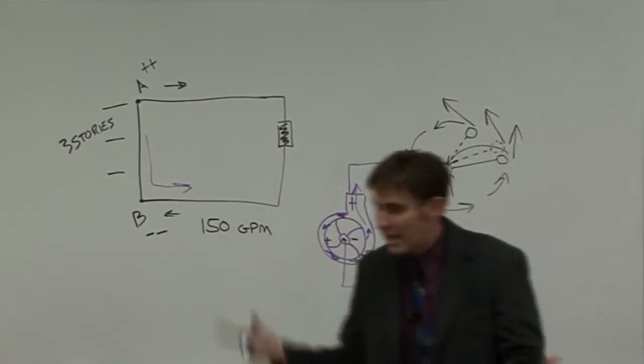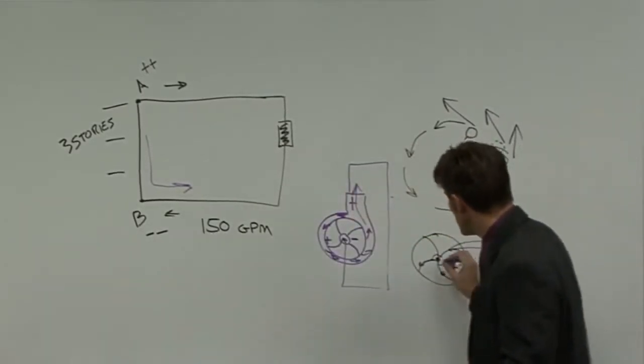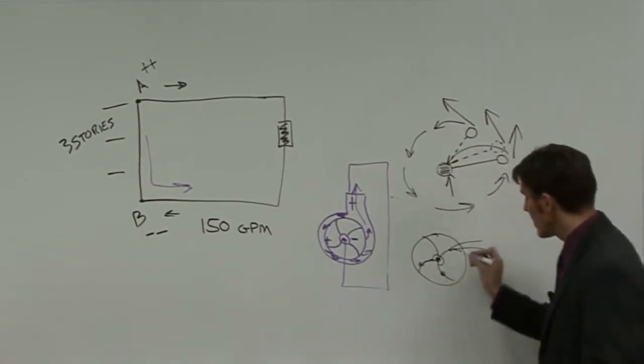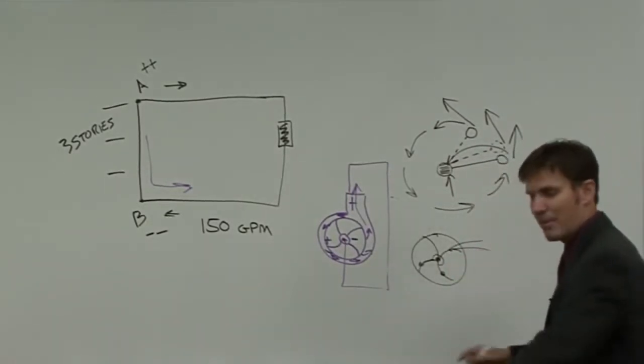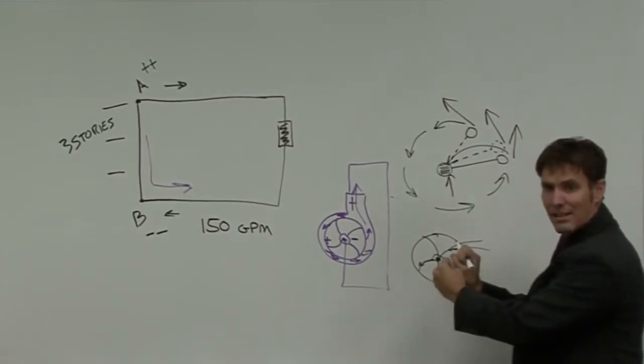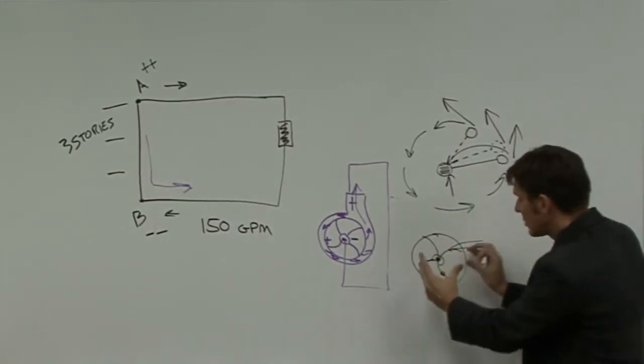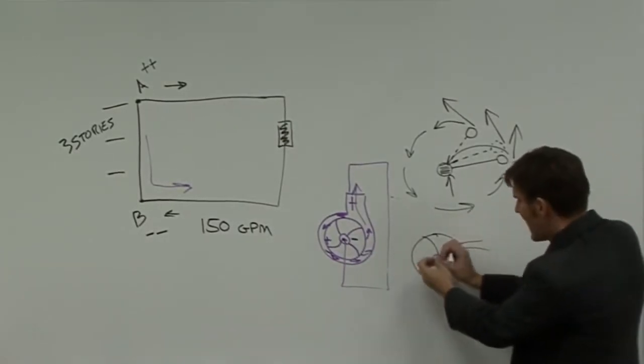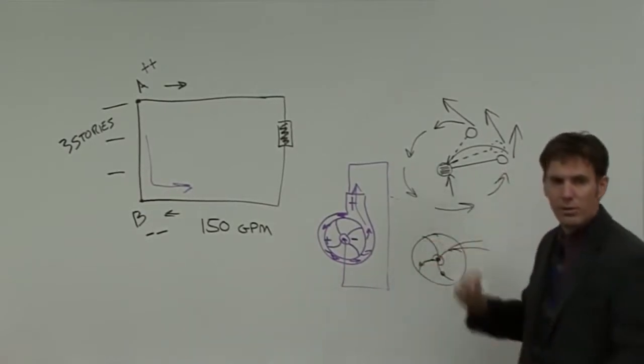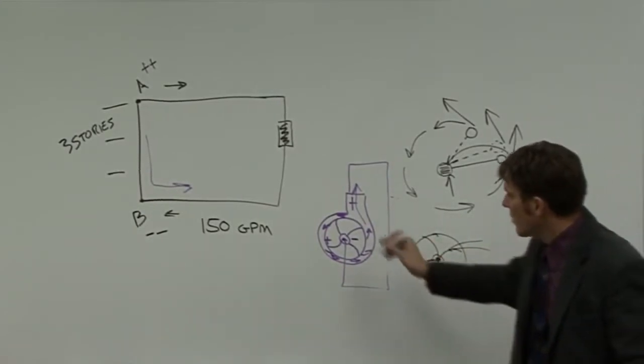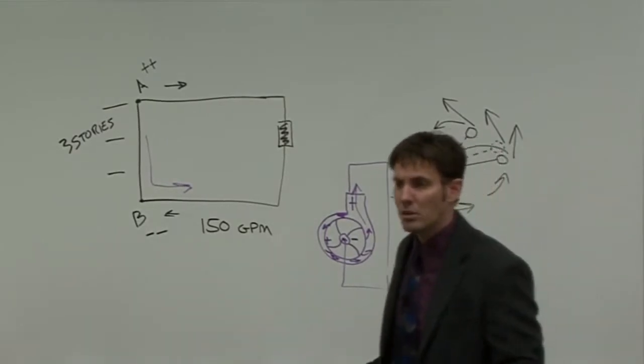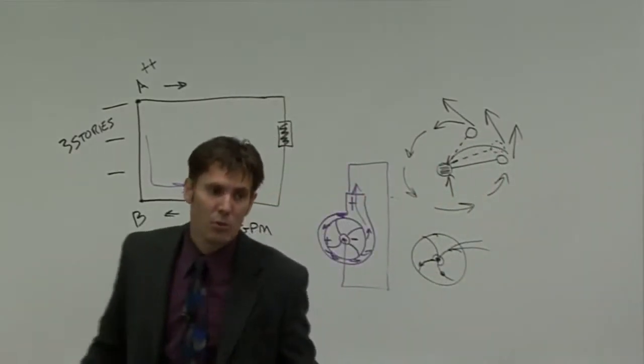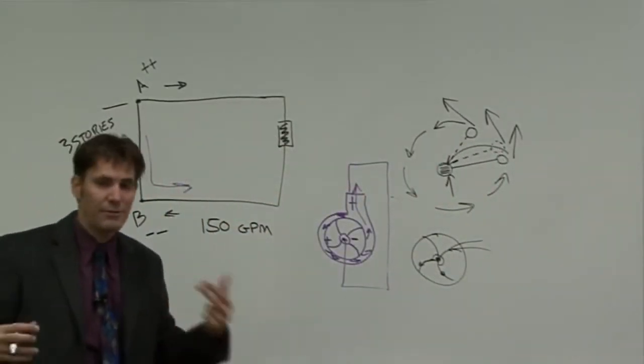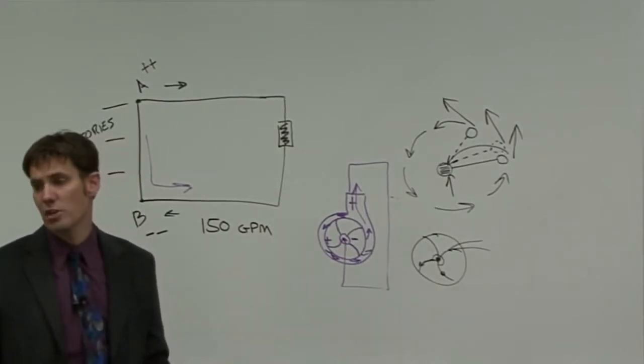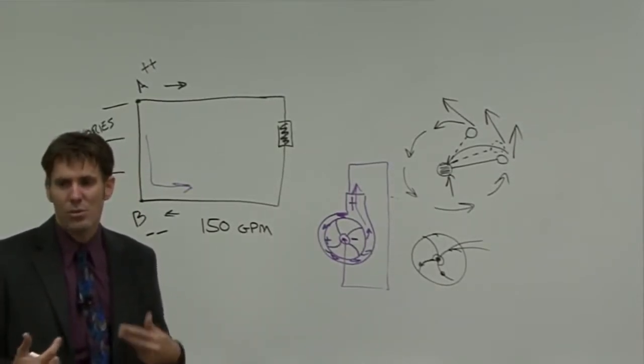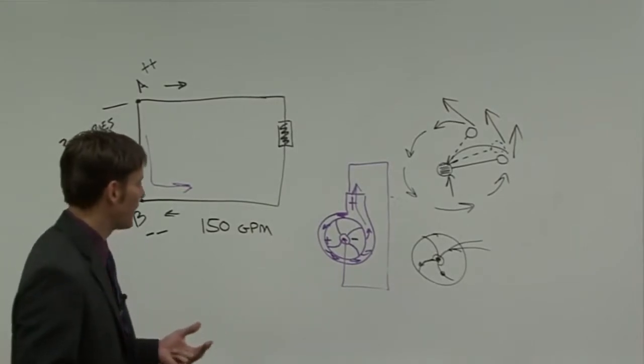I'm still moving in a centrifugal motion. If I spin this merry-go-round with my kids on it faster and faster, but then I stop and then spin it backwards, it doesn't suck them back into the middle. We still create that centrifugal pressure and still throw everybody off. We're just doing it in the reverse direction. So if I rotate a pump backwards, we're still going to have flow. But the problem is we don't know what that flow rate is because the manufacturer didn't give us the published curves of doing that. So we're not getting anywhere near the flow that we want.